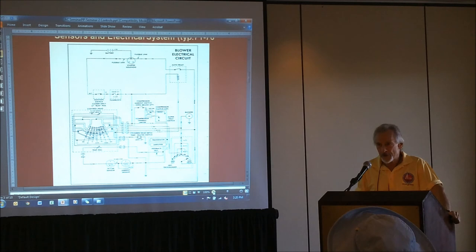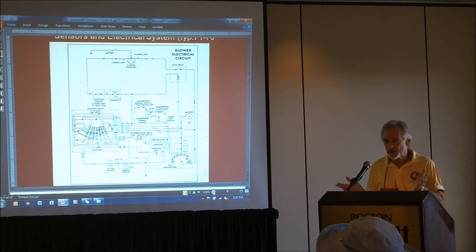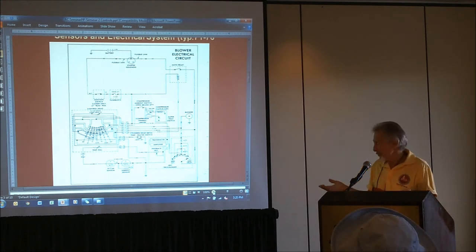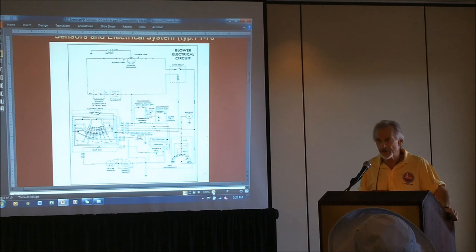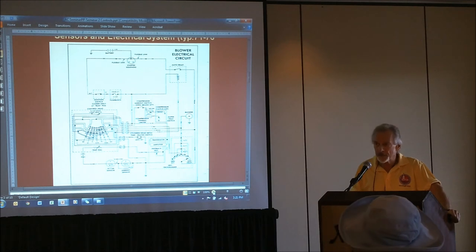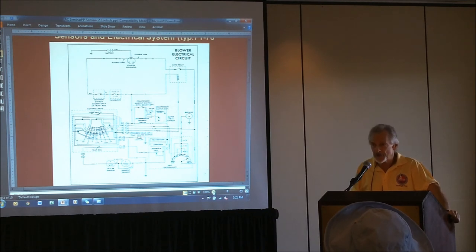Refrigerant compressors work on what they call a compression ratio, and that's the difference between low pressure, the suction pressure, and the discharge pressure. In this case we're just changing the discharge pressure, so we're raising the compression ratio. As the discharge pressure goes up, the efficiency of any compressor goes down, regardless of what refrigerant it's pumping. And with 134A, a compressor designed for refrigerant 12 loses about 18 to 21% of its efficiency.